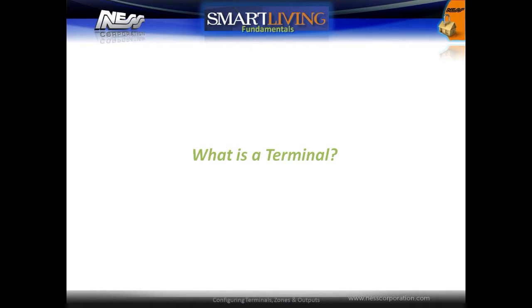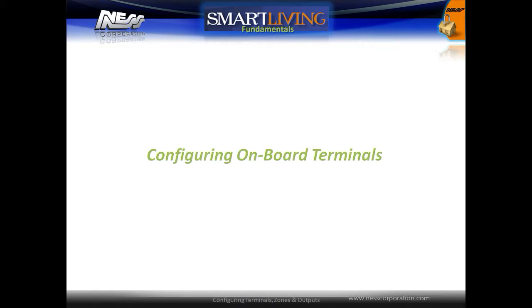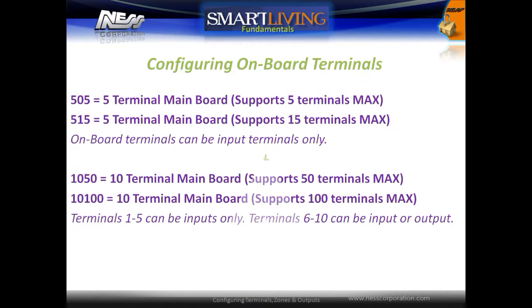Terminals are the physical connectors on the main board and expanders. Terminals are labeled from T1 through to T10 and can be configured as either inputs or outputs. Terminals can be zone doubled to provide up to 10 zones off five terminals. The 505 and 515 panels have a total of five terminals on board, with the 505 being expandable to five terminals maximum and the 515 being expandable up to 15 terminals maximum.